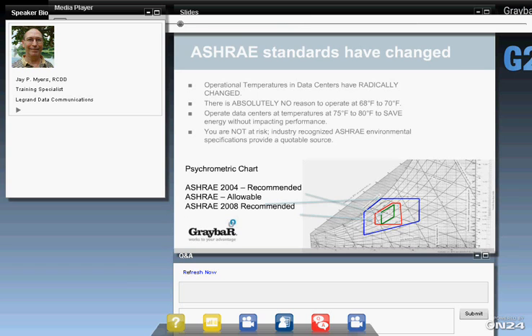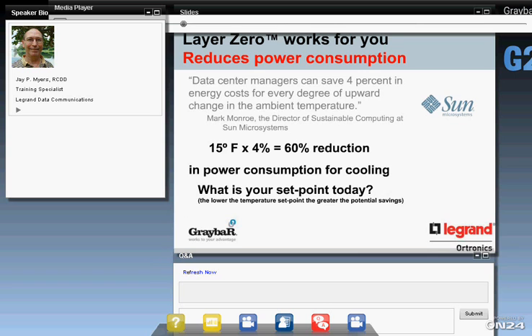Here, the axis across the bottom is temperature and up the side is humidity, and you can see how their envelope of recommended temperature and humidity has expanded greatly. This makes possible huge savings in electrical consumption. According to Mark Monroe, the director of sustainable computing at Sun Microsystems, you can save 4% in your energy costs for every degree upward change in ambient temperature. Every data center is different, and it's hard to predict exactly without a computational fluid dynamics study. But many of our customers anecdotally have told us they can raise their temperatures 10 or 15 degrees and still have acceptable equipment temperatures. That's a huge savings. The colder your set point is today, the more potential there is for savings.